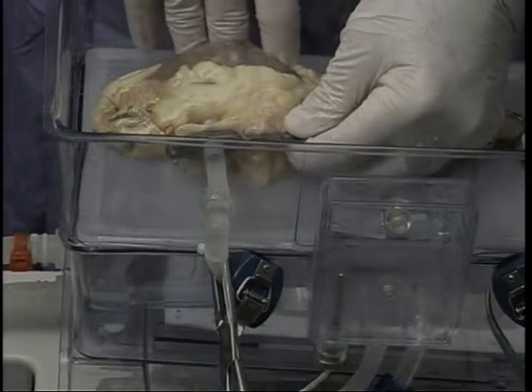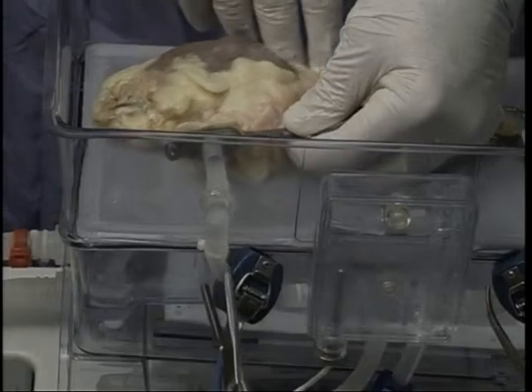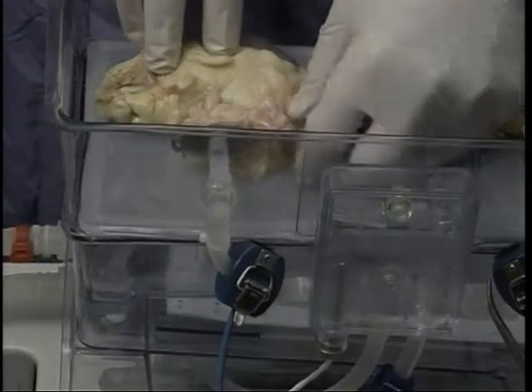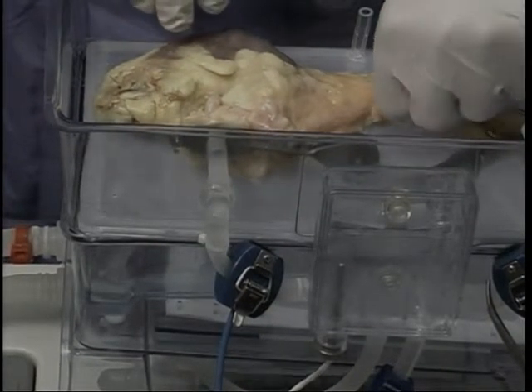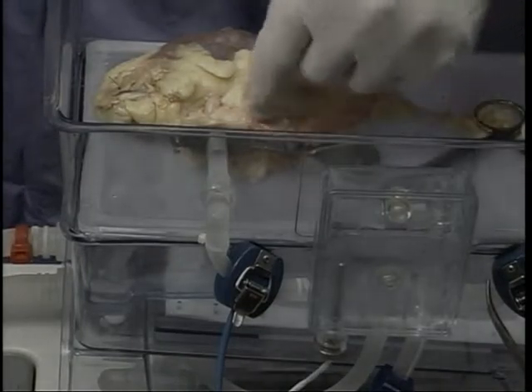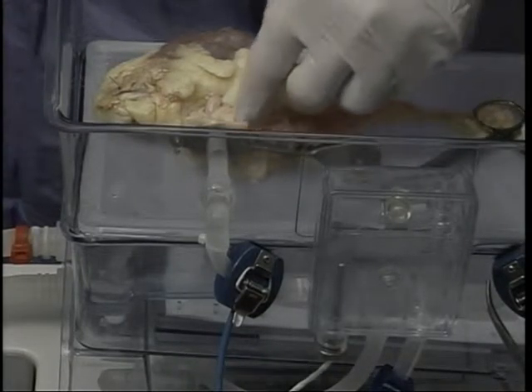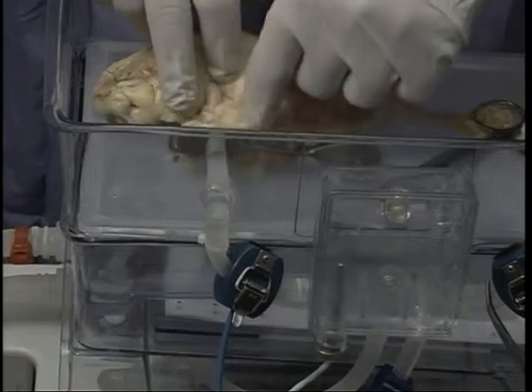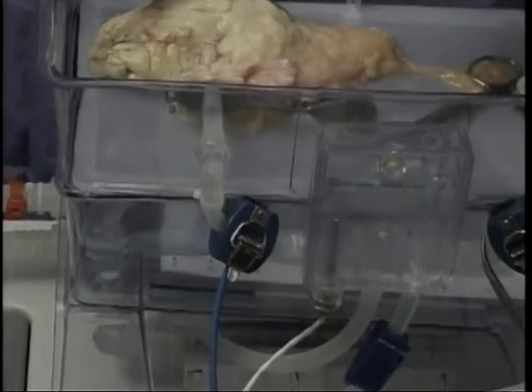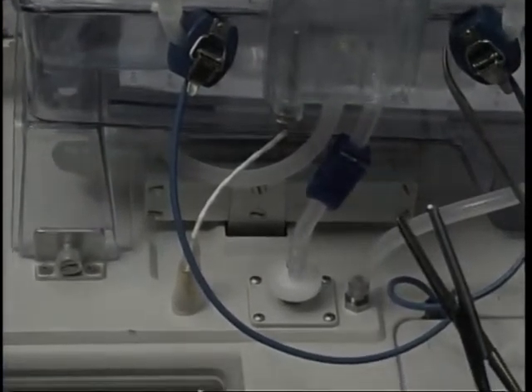Then the perfusionist is notified that the kidney will be placed on the pump and the clamp is placed into the arterial line. After the kidney is placed into the machine, then the perfusionist can increase the stroke volume, which increases the pressure to somewhere between 40 and 60 millimeters mercury.